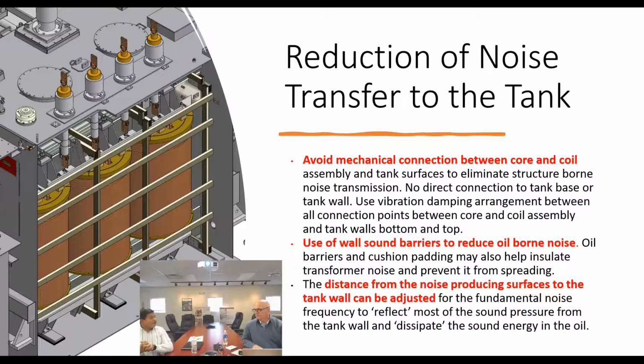So let's talk about reducing the noise of the transformer through the transformer tank. First, we know that the main vibrating elements are the core and the coil, mainly the core, and that noise is transferred to the tank wall. So the easiest way is that there should not be any connection between the core and coil and the tank. If there is no connection between them, there is no sound. That is the easiest way of doing it. But we also have to make sure that the transformer is suitable for transportation, because we don't want to damage the core and coil during transportation. That's why we have to connect the transformer core and coil assembly to the tank. So the other way we can do it is using a vibration damping arrangement between the connections.